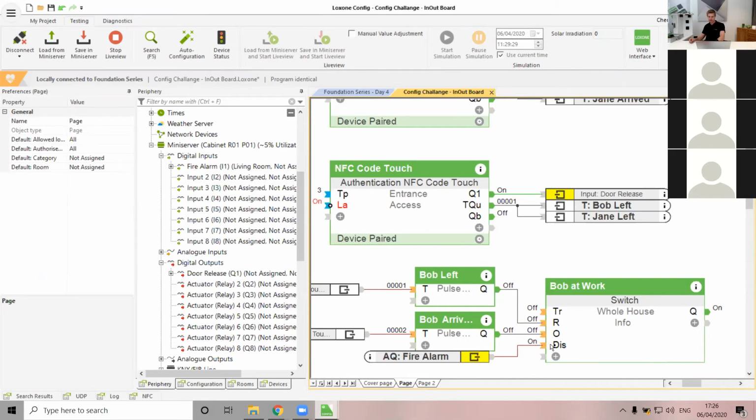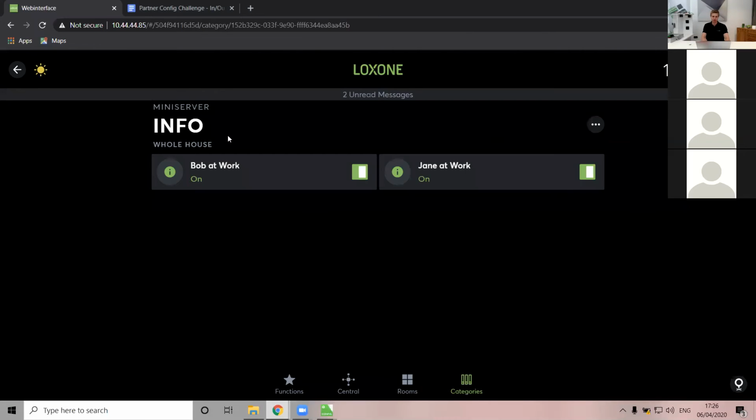And you can see that the reset actually came on, but that the output hasn't changed. That's because of the disable. I'm going to do that again. You can see reset is being triggered, but the output doesn't change. That input is being ignored due to the disable input currently being on. So in the user interface, what's happening is that we've frozen the state of these blocks, and hence we can now use that as a fire register.